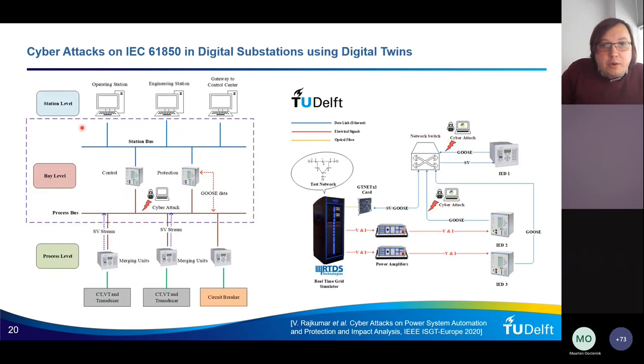Now, in our infrastructure, we can model a digital substation. So this is a schematic of the digital substation at process level, bay level, and station level. So we would have current transformers and voltage transformers to sense voltage and current waveforms. Then there are the merging units, which are intelligent electronic devices, that do the sampling of analog voltages and currents into sample values. So this would be all digital communications.